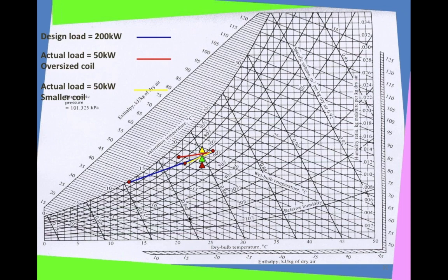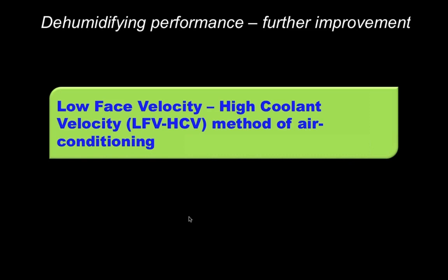So basically my space condition goes up and down a vertical line, the space temperature set point, depending on how my coil can perform. So the lower I can bring that point on that temperature of 24 degrees, the better I am. So what I've just shared with you is changing the surface area of the coil, taking a smaller coil, I would get a better coil performance. How am I going to do that in practice? I have a large cooling coil selected, a design for 200 kilowatts. It's installed. What I'm going to do with that?